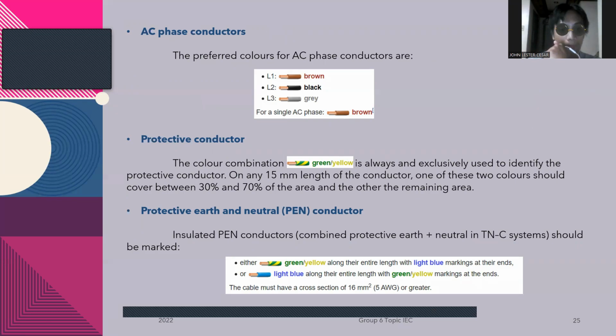Next is the protective conductor. The color combination green-yellow, as I've said earlier, is always and exclusively used to identify the protective conductor. On any 15 mm length of the conductor, one of these two colors should cover between 30% and 70% of the area, and the other the remaining area. Next is the protective earth and neutral, or PEN, conductor. Insulated PEN conductors, combined protective earth plus neutral in a TN-C system, should be marked either green-yellow along their entire length with light blue markings at their ends, or light blue along their entire length with green-yellow markings at the ends. The cable has a cross-section of 16 mm squared or 5 AWG or greater.